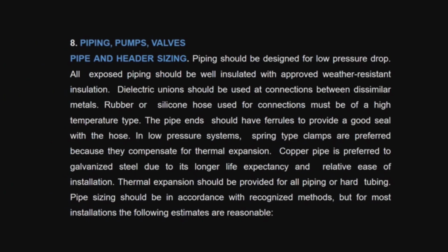The pipe ends should have ferrules to provide a good seal in low pressure systems. Spring type clamps are preferred because they compensate for thermal expansion. Copper pipe is preferred to steel due to its longer life expectancy and relative ease of installation. Thermal expansion should be provided for in all piping or hard tubing. Pipe size should be according to the recommended method, but on most installations the following are reasonable.